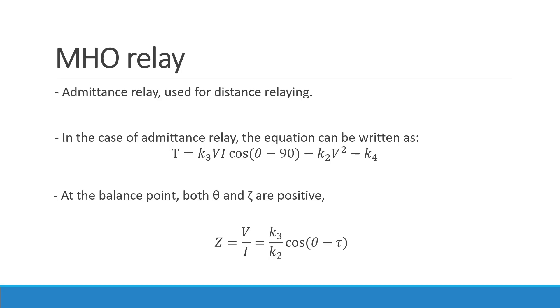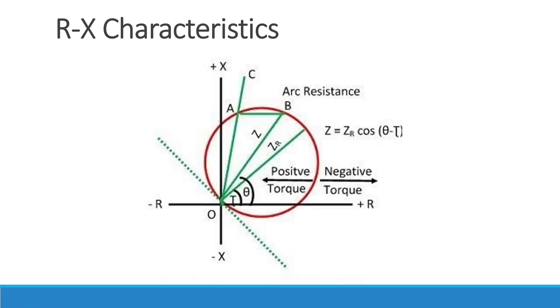The Mho relay is also called the admittance relay and is also used for distance protection. For the admittance relay, the torque equation can be rewritten as T = K3·V·I·cos(θ − τ) − K2·V² − K4. At the balance point, the impedance V/I is given by (K3/K2)·cos(θ − τ). In the RX plane, the Mho characteristic is also a circle but positioned in the positive or forward direction. Inside the circle is the positive torque region, outside is the negative torque region, and the setting impedance is given by Z = Zr·cos(θ − τ).